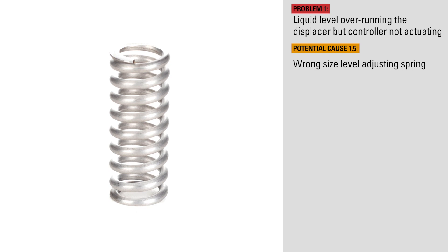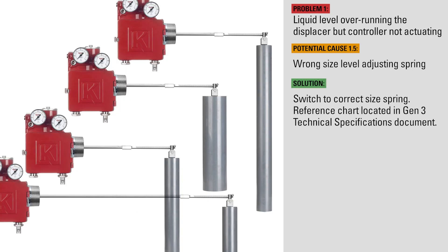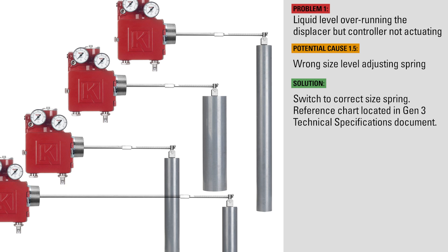Your displacer may be the right size, but you could have the wrong spring. Various combinations of displacer sizes and extension arm lengths could necessitate a heavier spring. This chart located in the Gen 3 Technical Specifications document specifies which spring you should use based on the displacer size and extension arm lengths. There are only two springs that could be used: the standard and the heavy spring.